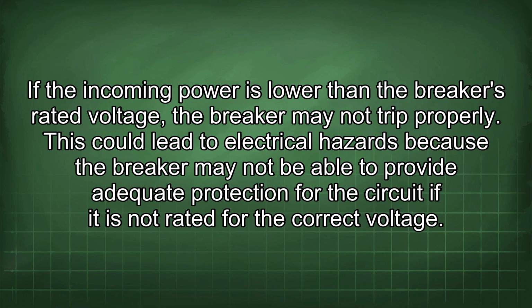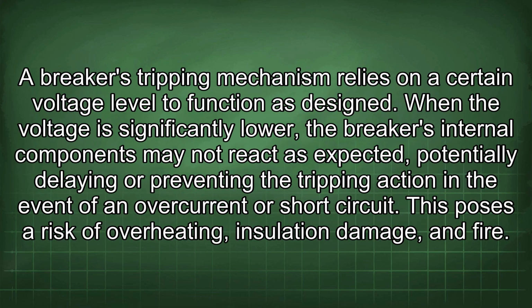This could lead to electrical hazards because the breaker may not be able to provide adequate protection for the circuit if it is not rated for the correct voltage. A breaker's tripping mechanism relies on a certain voltage level to function as designed. When the voltage is significantly lower, the breaker's internal components may not react as expected, potentially delaying or preventing the tripping action in the event of an overcurrent or short circuit. This poses a risk of overheating, insulation damage, and fire.